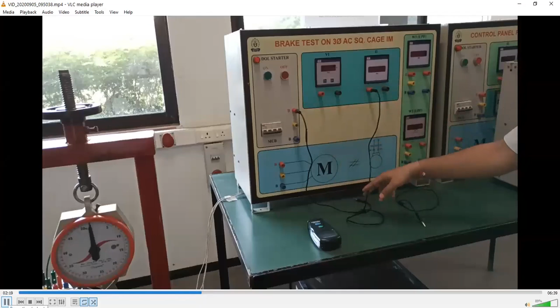See on the screen, current is now going to the ammeter. Now from the ammeter, it will go to the R phase of the wattmeter. Now from the R phase of the wattmeter, it will go back to the motor. And as you can see, your motor is over here. So from this panel, connections are going to the motor, which I already showed you. And I also showed you the motor connection, which is connected in delta. So our motor is connected in delta, so we do not need a neutral over here. Now let's go to the Y phase. As you can see, that Y phase.